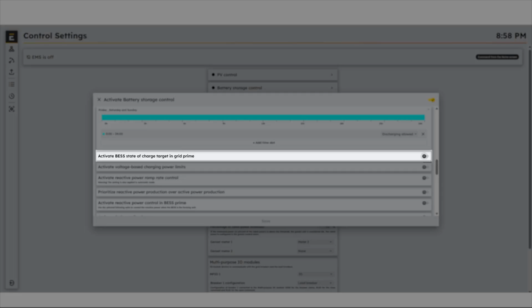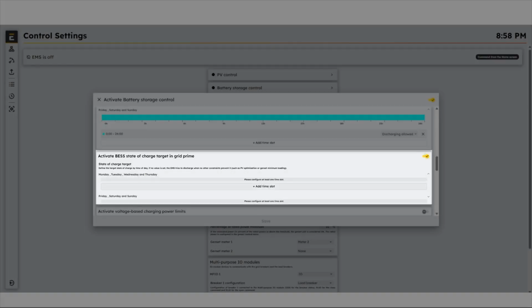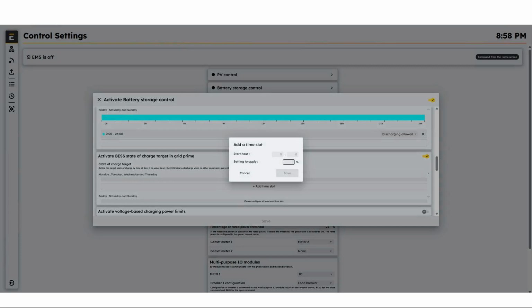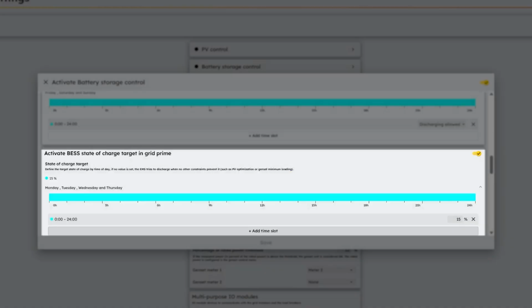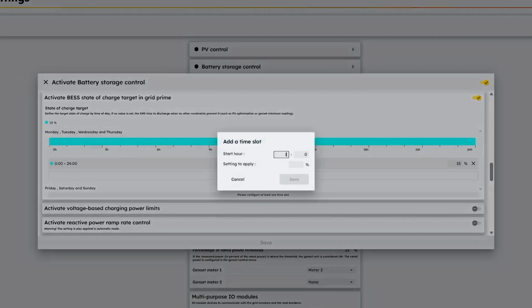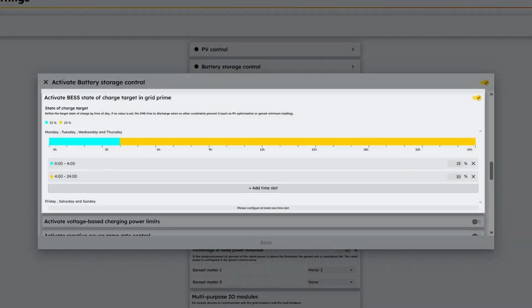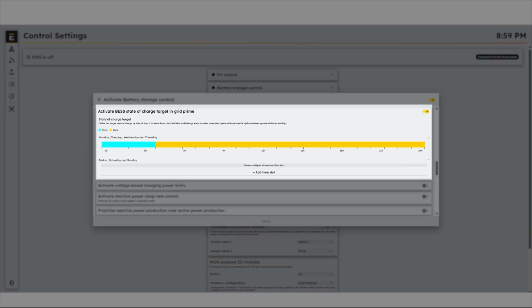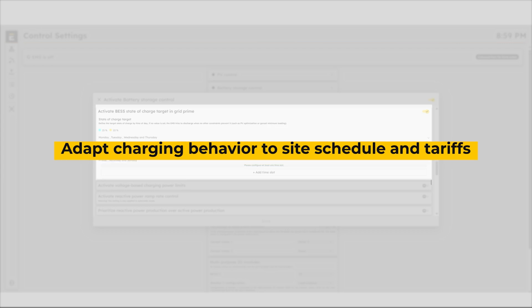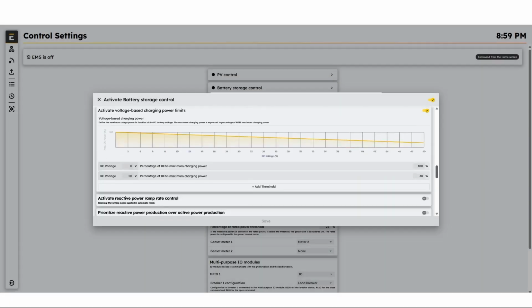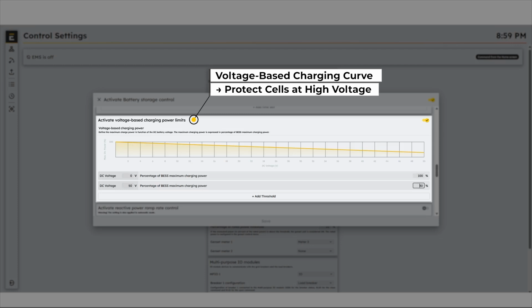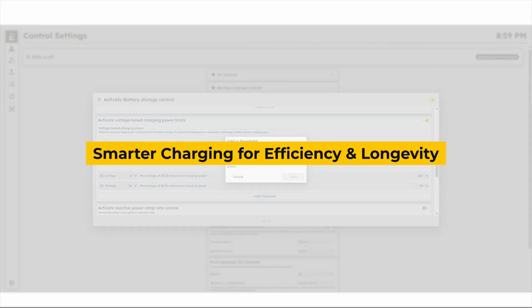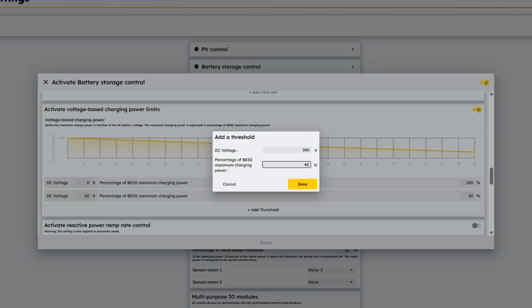The State of Charge target allows you to schedule specific charge levels for the battery at different times of the day or week. The EMS will automatically try to reach the defined SOC for each period by charging or discharging the BESS accordingly. This feature is typically used in Grid Prime or Genset Prime modes to define a daily charge-discharge profile based on site operation or tariff periods. The voltage-based charging power limit dynamically reduces the charging rate as the battery voltage increases, preventing cell overstress and extending battery life.